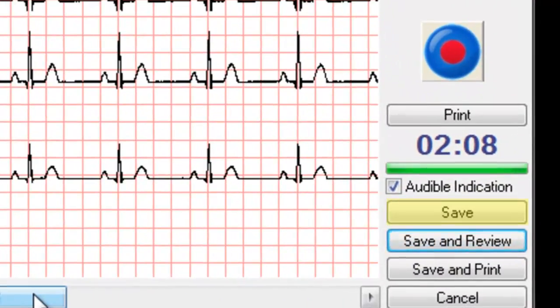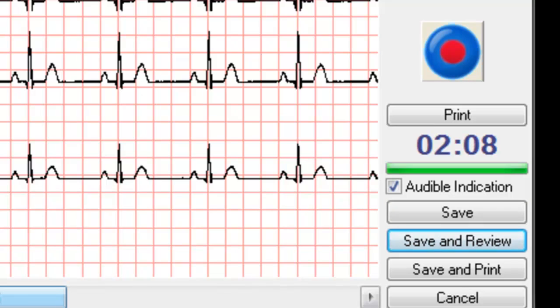Click Save to begin the filing process for your chosen segment. A further option that becomes available by clicking the Stop button is the Print button directly beneath it. If this is pressed, it will print off the trace for the whole of the monitoring duration, to a maximum of 15 minutes.